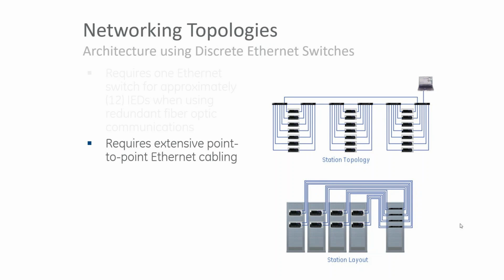The problem with these discrete Ethernet switch topologies is that there are a lot of point-to-point connections, requiring a lot of point-to-point Ethernet cabling. For RJ45 this is probably not a big deal if the devices are within the same switchgear lineup, since the runs are short and can be shielded. But with fiber optic and longer runs, it can be more difficult because of all the splicing and cable routing required.